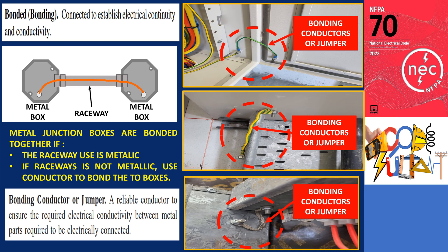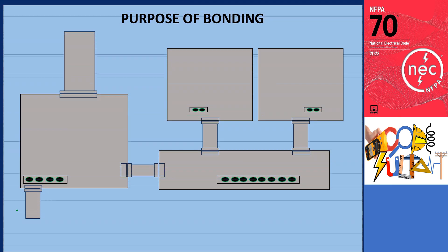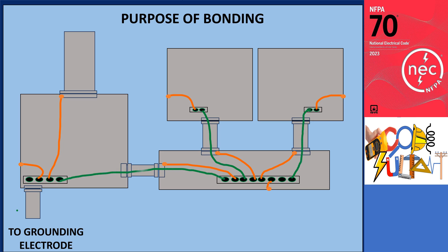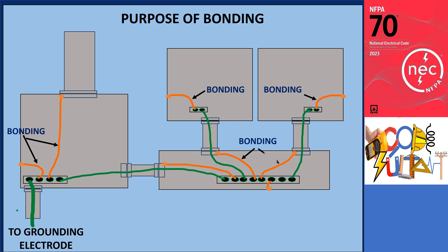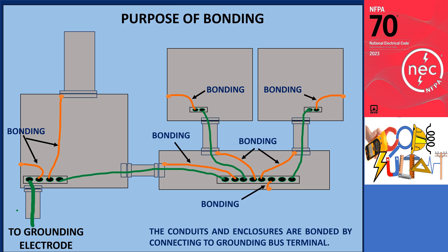It's important to remember that bonding two pieces of equipment together does not automatically mean that both pieces are grounded. In another illustration, we can see conduits and enclosures that are bonded by connecting them to a grounding bus terminal. The purpose of bonding is to connect two or more conductive objects together in order to ensure the electrical continuity of the ground fault current path. This provides the capacity and ability to safely conduct any fault current that may be imposed and minimizes voltage differences between conductive components.